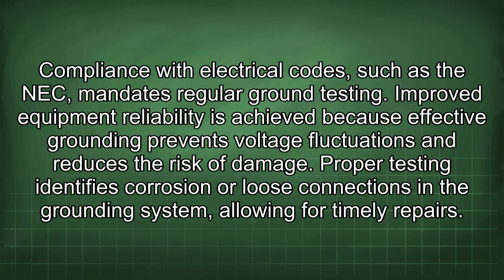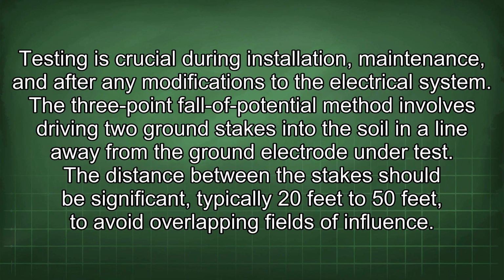Improved equipment reliability is achieved because effective grounding prevents voltage fluctuations and reduces the risk of damage. Proper testing identifies corrosion or loose connections in the grounding system, allowing for timely repairs. Testing is crucial during installation, maintenance, and after any modifications to the electrical system.